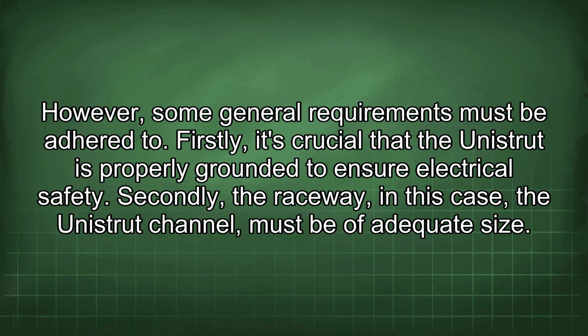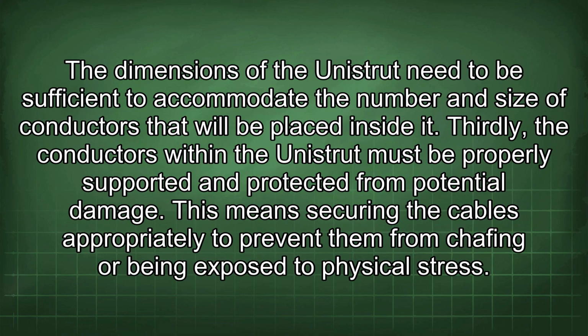Firstly, it's crucial that the Unistrut is properly grounded to ensure electrical safety. Secondly, the raceway, in this case the Unistrut channel, must be of adequate size. The dimensions of the Unistrut need to be sufficient to accommodate the number and size of conductors that will be placed inside it. Thirdly, the conductors within the Unistrut must be properly supported and protected from potential damage. This means securing the cables appropriately to prevent them from chafing or being exposed to physical stress.